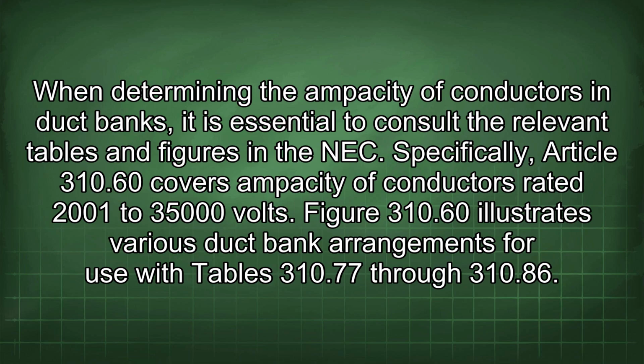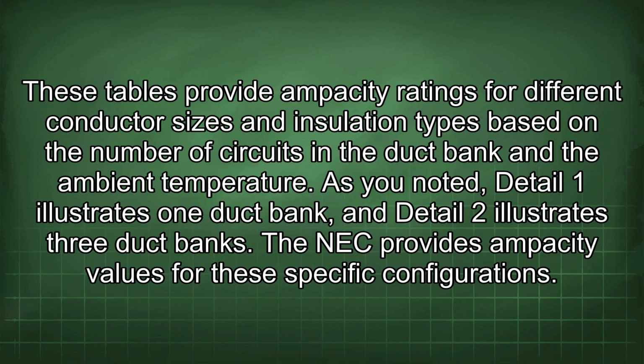When determining the ampacity of conductors in duct banks, it is essential to consult the relevant tables and figures in the NEC. Specifically, Article 310.60 covers ampacity of conductors rated 2001 to 35,000 volts. Figure 310.60 illustrates various duct bank arrangements for use with tables 310.77 through 310.86. These tables provide ampacity ratings for different conductor sizes and insulation types based on the number of circuits in the duct bank and the ambient temperature.